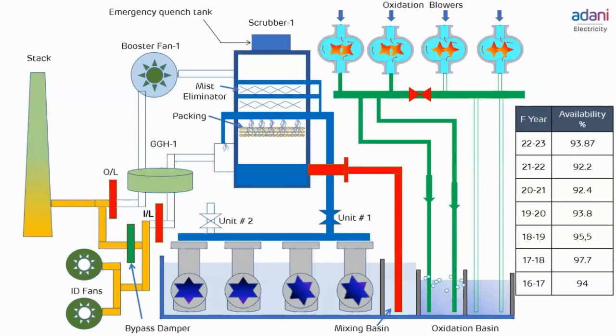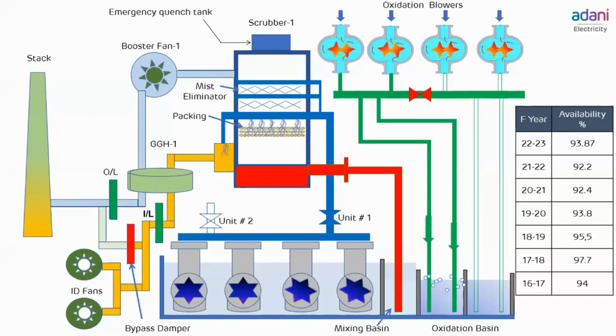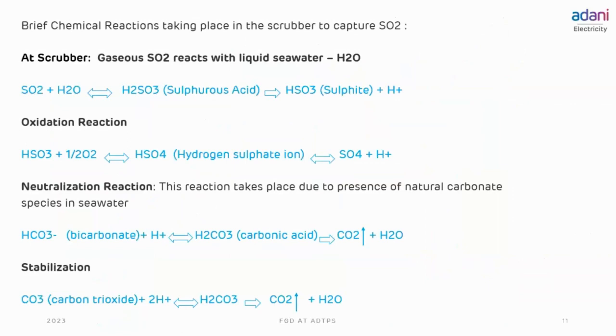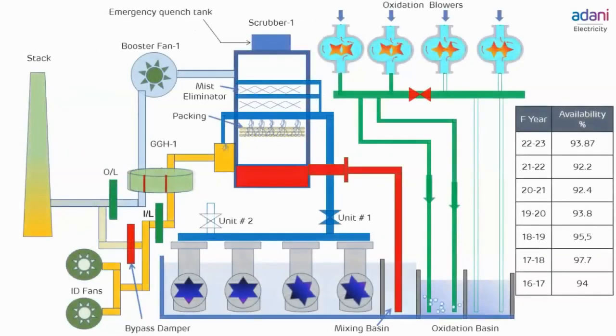The flue gas from boiler first enters into the gas to gas heater, where it is cooled from 135 degrees to around 92 degrees Celsius by outgoing gases. In turn, the outgoing gases are heated from 44 degrees to 86 degrees. The GGH is a rotary heat exchanger, and it handles large volume of flue gas. From GGH, the gas is then taken into the scrubber.